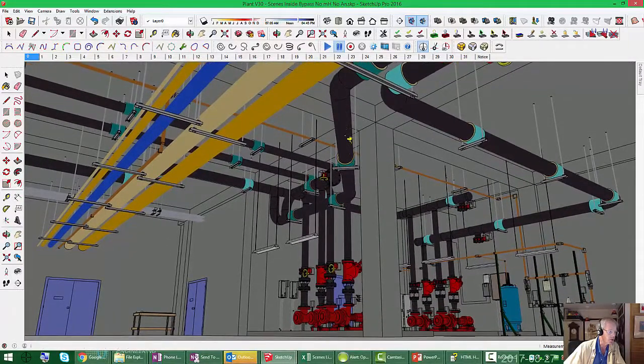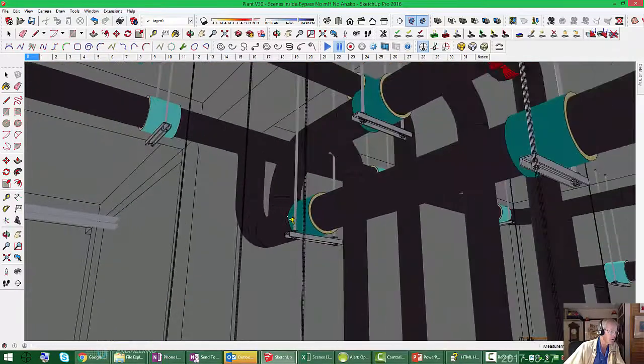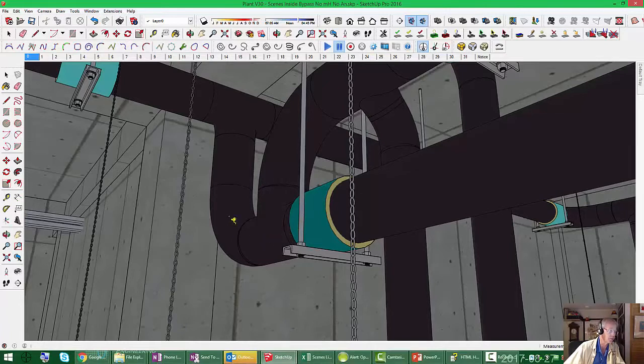We're coming along here, the pipe offsets a little bit. In a system diagram, you aren't so worried about the elbows. The elbows aren't very important in a system diagram other than to organize it. They're very important in a pump head calculation, but not that important when you're doing a system diagram. So, if I was doing this so far, where I'm running my little cursor along, that would have just been a straight line. And it would continue to be a straight line until I got to here. Now I got a T. So my straight line becomes two straight lines. And I follow one branch or the other.